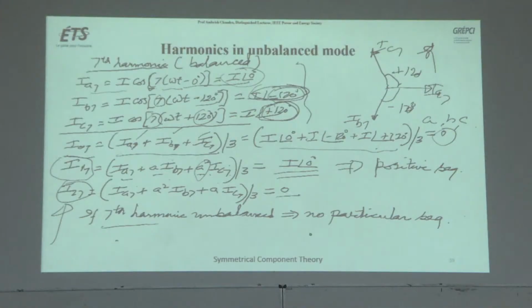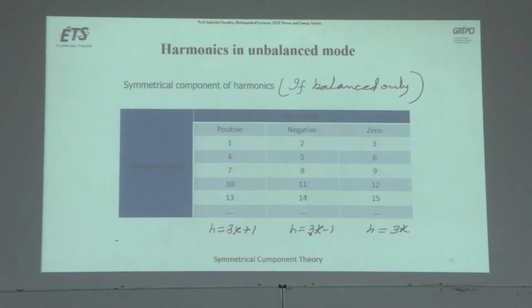So this is a very important thing to verify. And finally, what you can do, you can make a table. Sequence of the harmonic order, 1, 2, 3, 4, 5, 6, 7, 8, 9, 10, 11, 12, 13, 14, 15. So this is how you can write the table, and you can see which harmonic is positive sequence, which harmonic is negative sequence. Okay, so now you will say, oh, this is a long table.